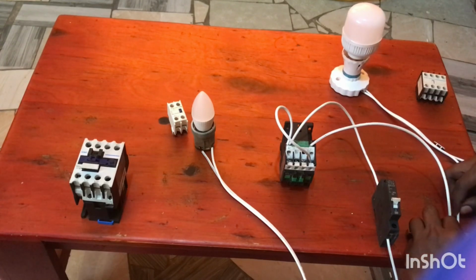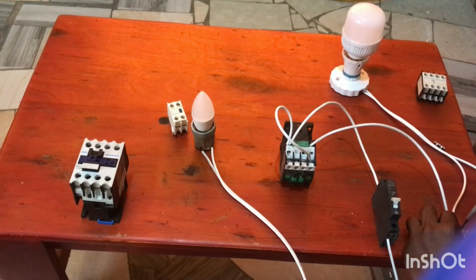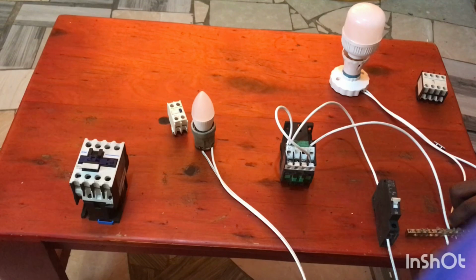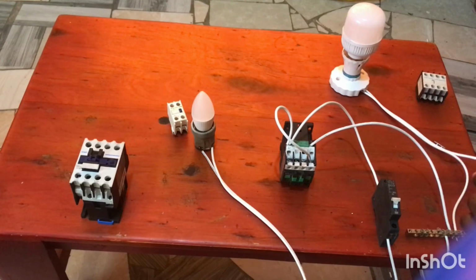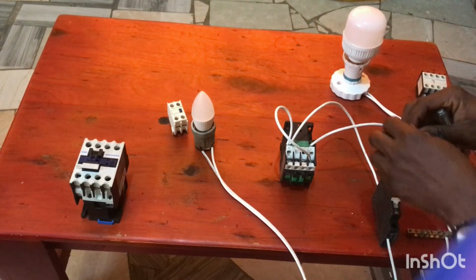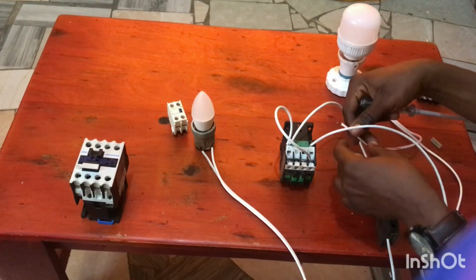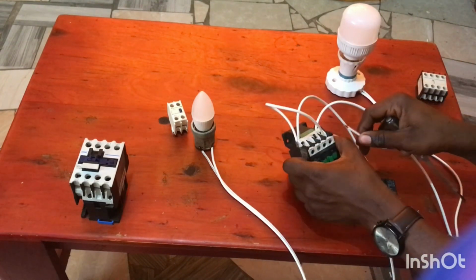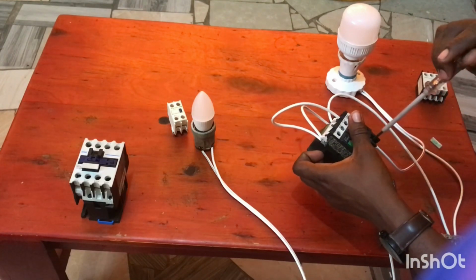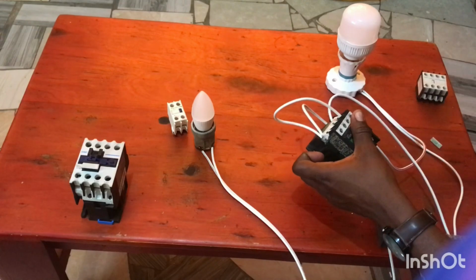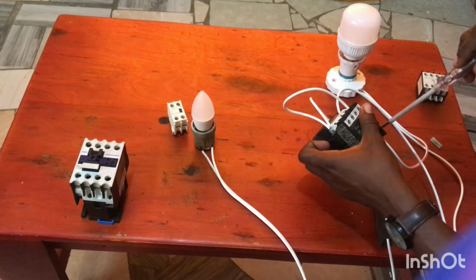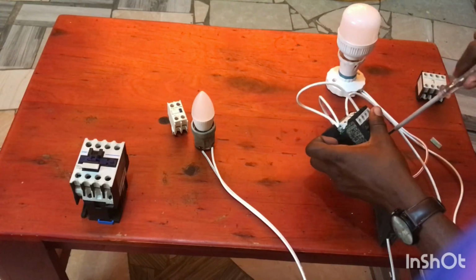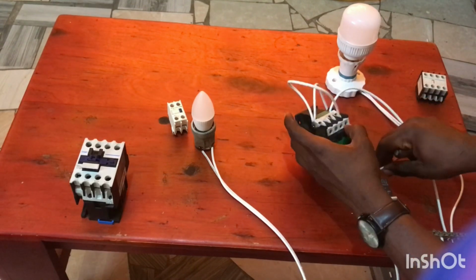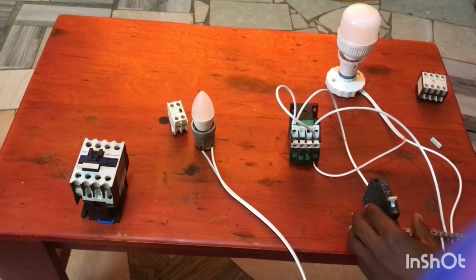So for my light cable, I'll start with the ground. Ground will go direct to the neutral bar. So I'll connect the ground here from the light. Then the live cable will go to the outlet of the normally open down here. Remember, the normally open has no power when the contactor is at rest, so we don't expect any power coming from the normally open contact. The light remains off as long as the contactor is not energized.